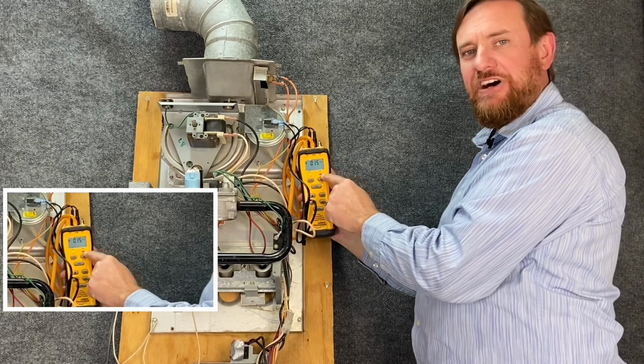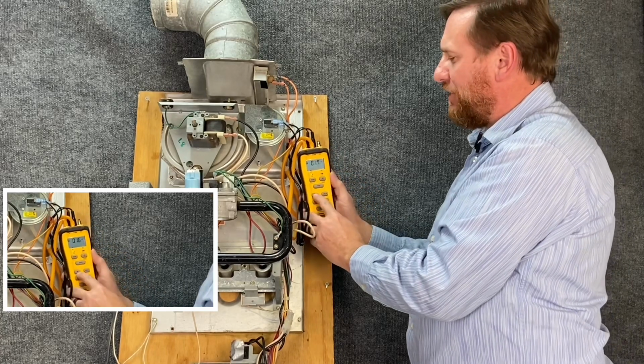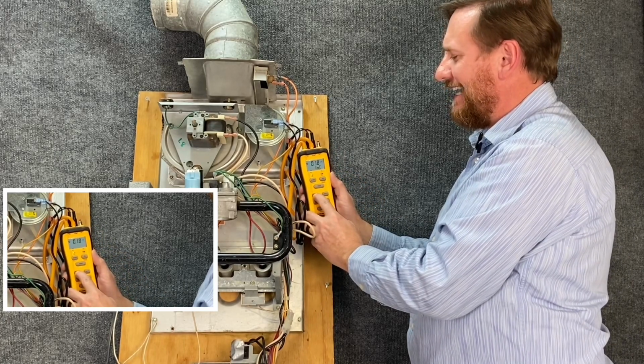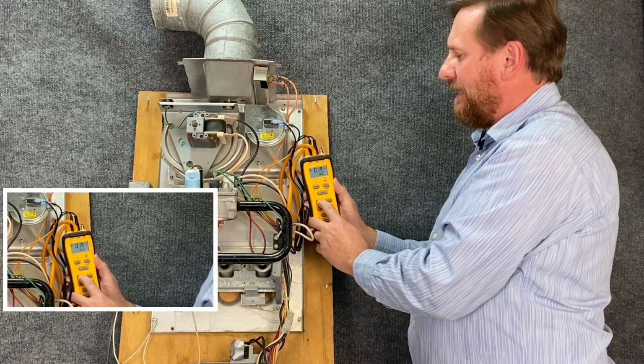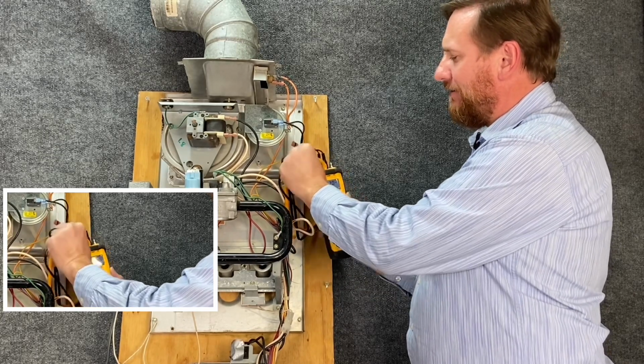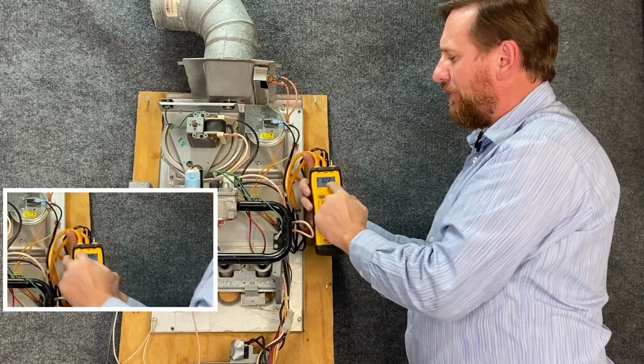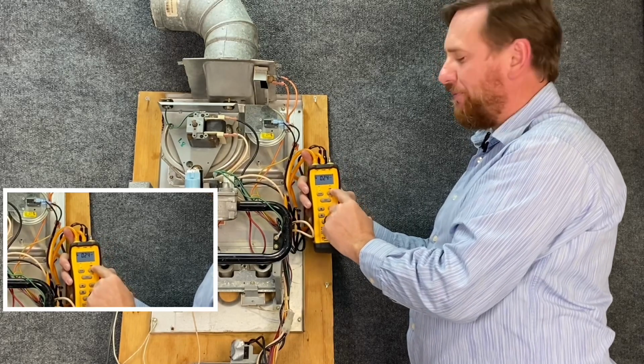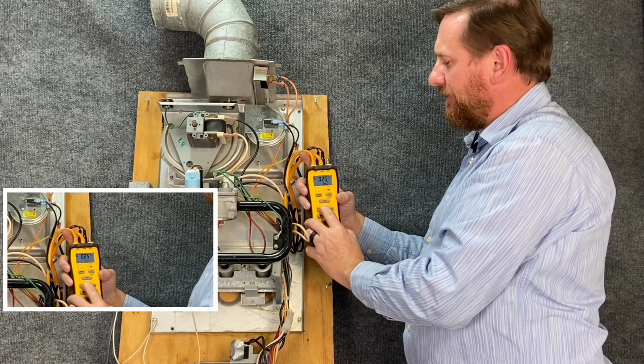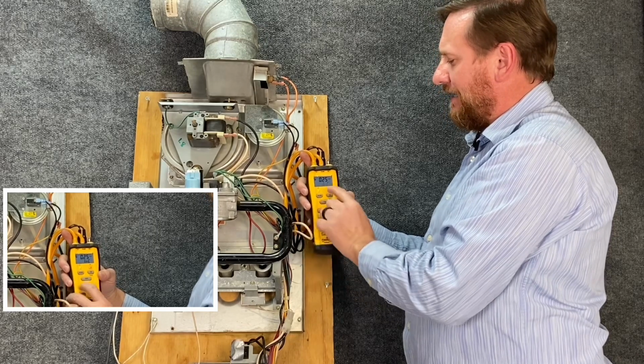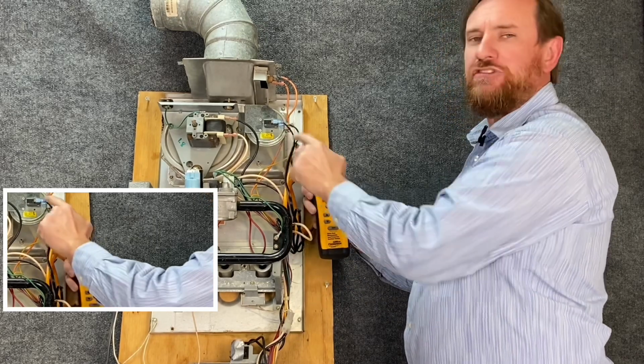The light is off. So I'm going to increase my pressure. So I'm going to press the up button, INC, increase. Now I'm at, we got to make sure we're not kinked. My hose is kinked there. So we're at 0.2 and my switch is still open. So we're going to increase it even more. And now we're at 0.25 and my switch closed.